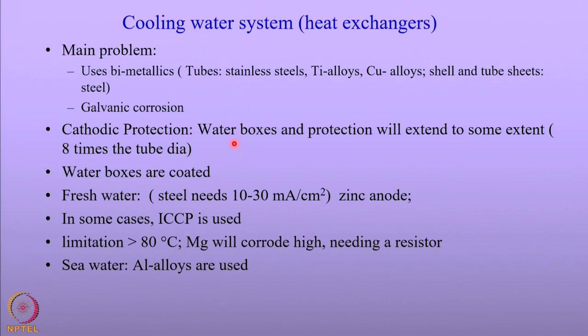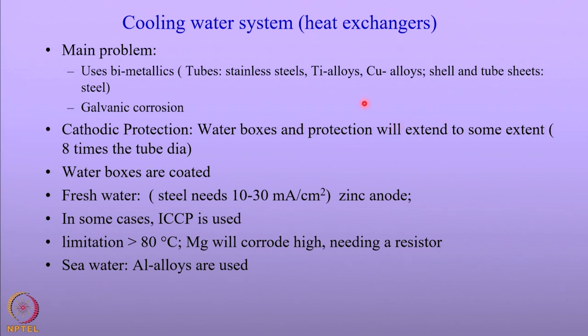Let us move on to the next topic — the cooling water system, where heat exchangers are used and these heat exchangers require cathodic protection. The main problem is that heat exchangers use bimetallics. The tubes are mainly stainless steels, titanium alloys, and copper alloys, while the shell and tube sheets are made of steel. Therefore, galvanic corrosion occurs and cathodic protection is applied to prevent it.